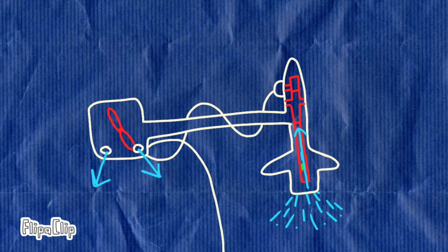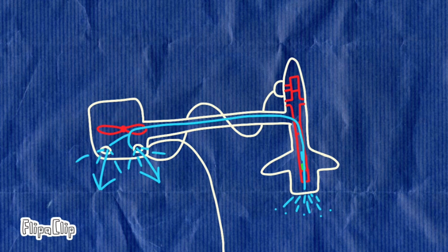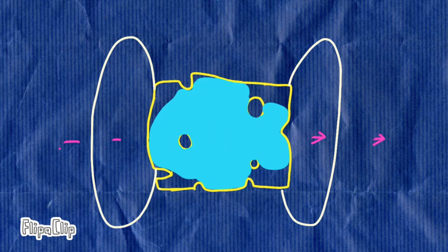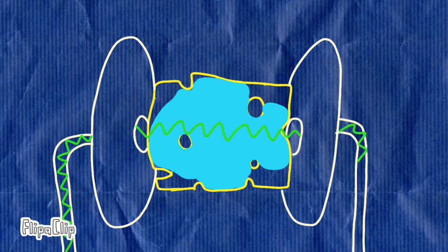The fan spins and creates a vacuum near the main opening. This draws outside air in. The air travels through the filter and over the polymer. If the air contains moisture, it gets absorbed by the polymer, and it pushes the plates farther apart. With the expanded polymer, the current will take longer to travel through the conductive material. The time is measured to calculate moisture in the air, and the information is sent to the computers.